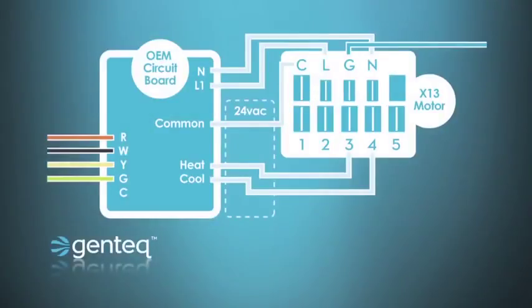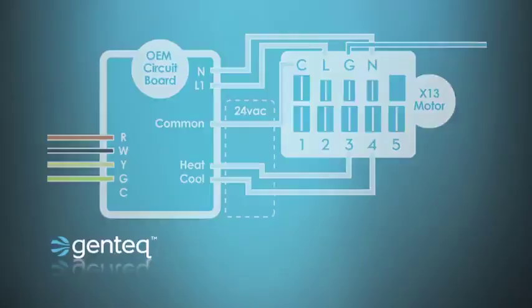We'll need that for the schematic, the voltage on each one of the taps, the purpose of each one of the taps, heat or cool, and the sequence of operation of the system so that we know when the voltage should come from the manufacturer's control board and go to the motor. There's two different ways that manufacturers are going to run the wires from the control board to the motor. One way we see here, they have a heat and a cool tap on the OEM circuit board, and they've run those two wires over to the X13 motor. But even from this diagram, we can't tell, are all 5 taps on the motor programmed or are just taps 2 and 3 programmed. So this schematic would be necessary to understand that if we want to make speed changes, we'd have to make them at the motor, and to make those changes we'd need to find the chart in the book that tells us what taps are programmed and what their other purposes are.